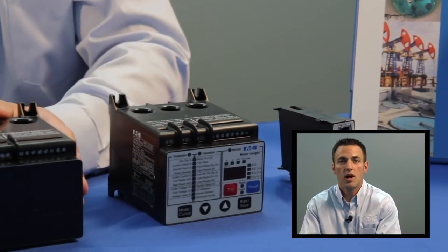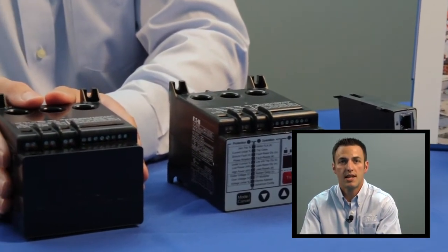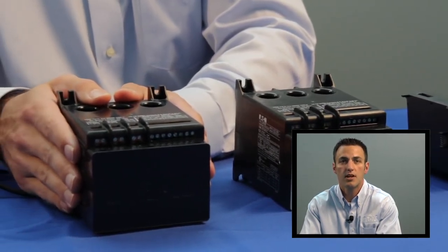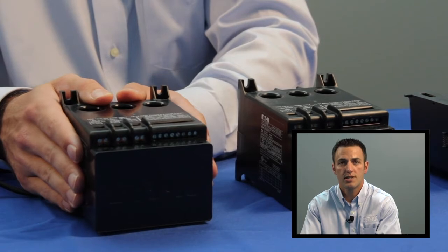The control power model draws its power from 120 volts AC. What this means is that a user can configure the device with only control power present — motor voltage does not need to be present.